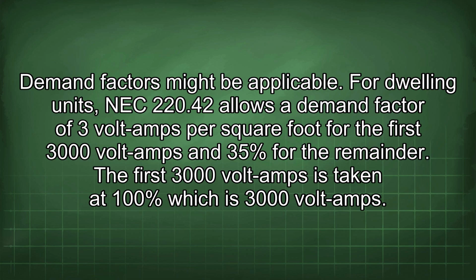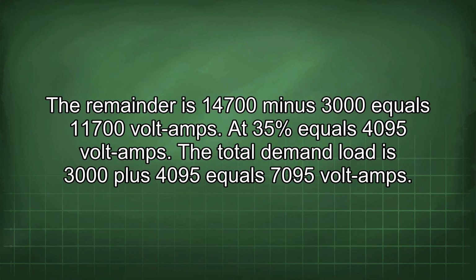Demand factors might be applicable. For dwelling units, NEC 220.42 allows a demand factor of 100% for the first 3000 volt-amps and 35% for the remainder. The first 3000 volt-amps is taken at 100%, which is 3000 volt-amps. The remainder is 14,700 minus 3000, equals 11,700 volt-amps. At 35%, that equals 4,095 volt-amps. The total demand load is 3000 plus 4095, equals 7095 volt-amps.